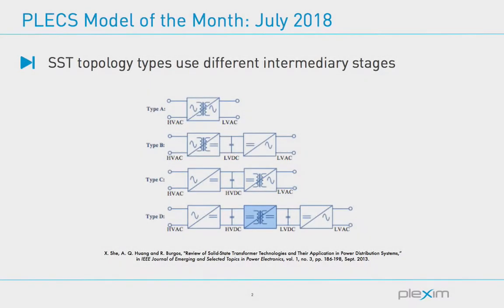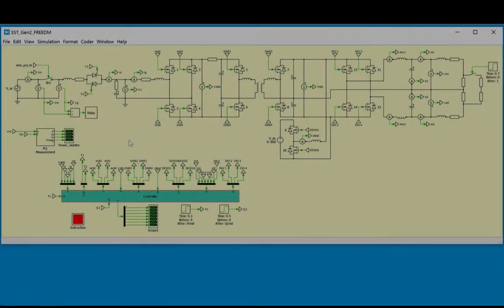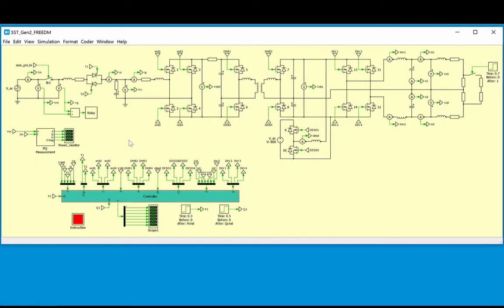There are various SST topology types, and this particular model employs what is known as a Type D SST, where there are three intermediary stages. Looking at the model, we see that there is a single phase mains, in this case operating at 7.2 kV and 60 Hz. Between the grid and the SST is a fault isolation device, or FID.